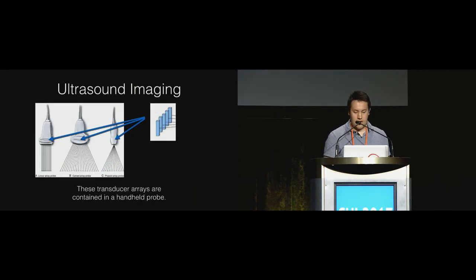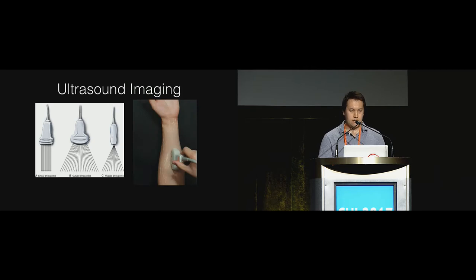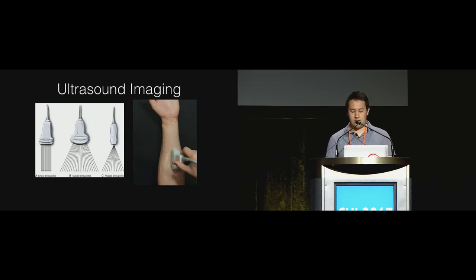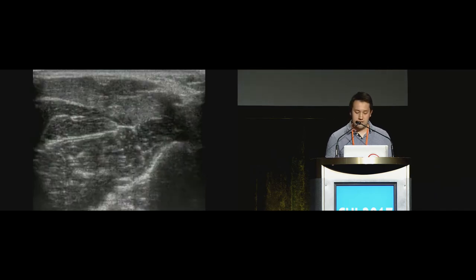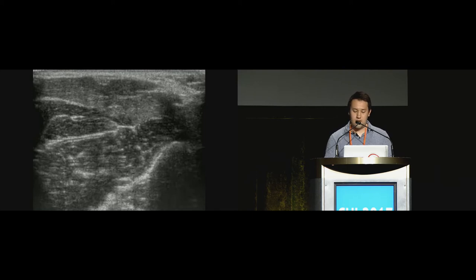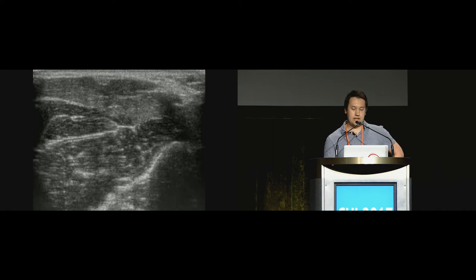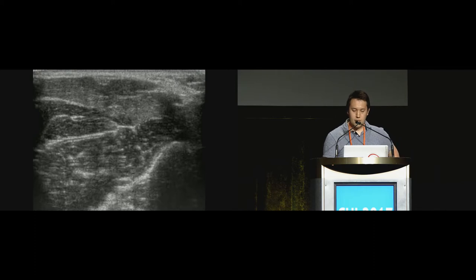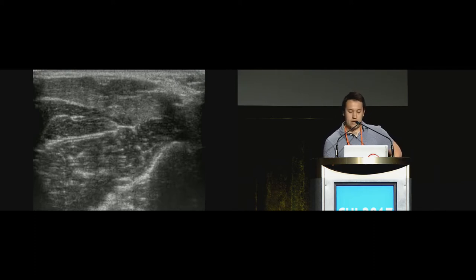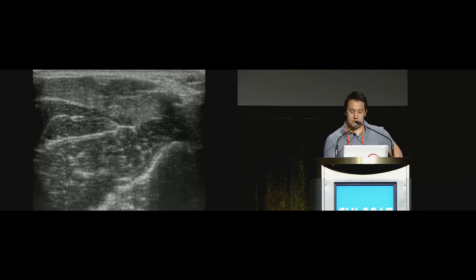These transducer arrays are housed in a hand-held probe which may come in many shapes and sizes. When the probe is held to the skin, the underlying tissue can be imaged. You get an image that looks a bit like this. The probe surface is towards the top and these images are quite hard to interpret but basically the bright areas indicate boundaries where there is a change between different types of tissues. For instance in the bottom right, the black glob there is the bone. Images can be obtained at multiple frames per second.